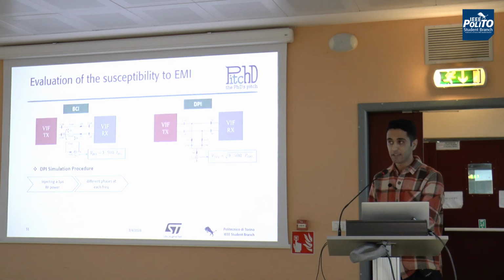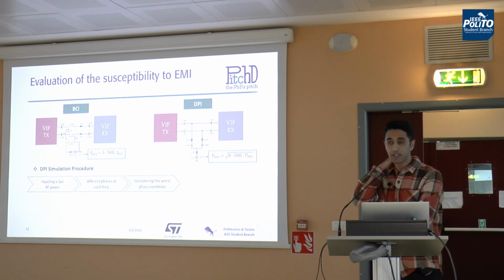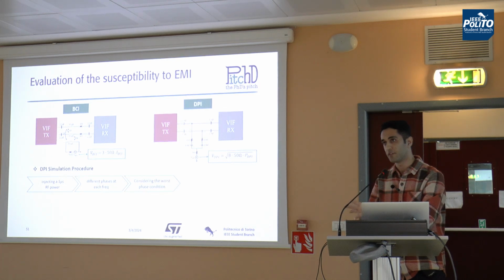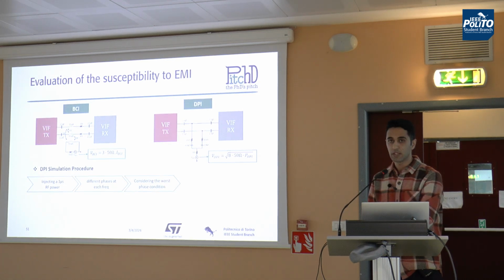Then at each frequency we change the initial phase of the disturbance to see if it affects the results, and then we consider the worst case of each different phase in each frequency for the evaluation, and then we increase the power level to see if the communication is correct or not.